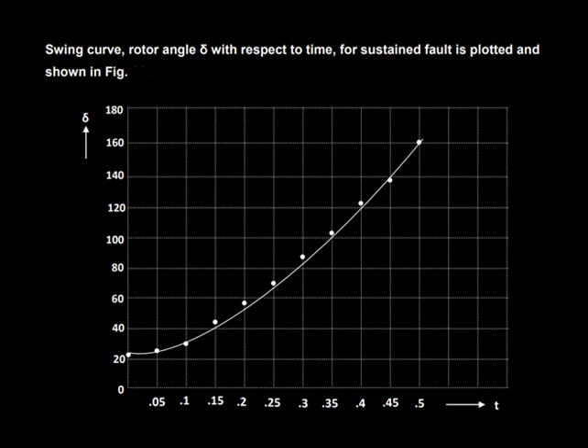From this process you can get a curve — a plot between delta and time. This curve has been discussed in earlier lectures. Considering the fault up to 0.5 seconds: for a sustained fault, delta continues to increase and you can predict it going up to around 160 degrees, which leads to asynchronous operation. This is a paper-based prediction showing the system will lose stability if the fault is sustained.